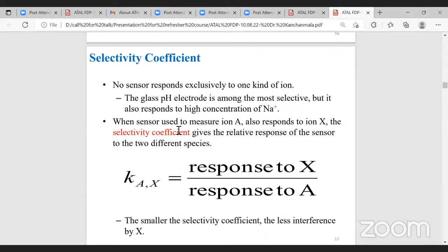Now, how to deal with this? In this case, you need to know the selectivity coefficient. When you develop a sensor, you need to see what the selectivity coefficient value of your sensor is. Now, what is the selectivity coefficient? When a sensor is used to measure ion A, but it is responding to X also, the selectivity coefficient gives you the relative response of the sensor to two different species. So on the numerator, you will have the interfering ion, whereas on the denominator, you have the ion which you wanted to measure. The smaller the selectivity coefficient, the less the interference. I hope you understood how important the selectivity coefficient is in developing a sensor. You wanted to measure A, that's why the K value should be as small as possible.